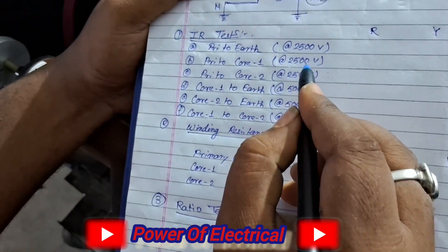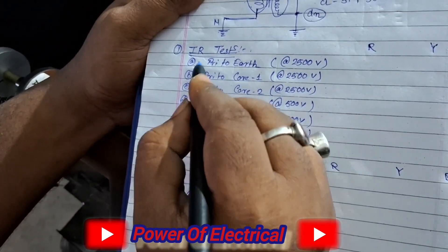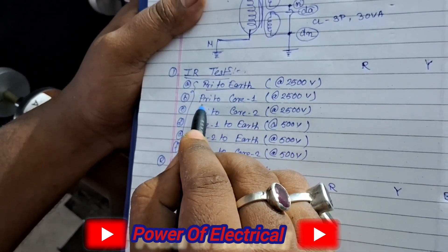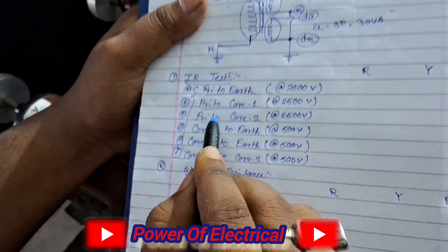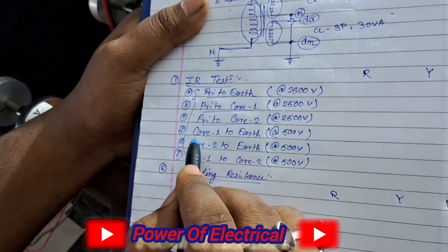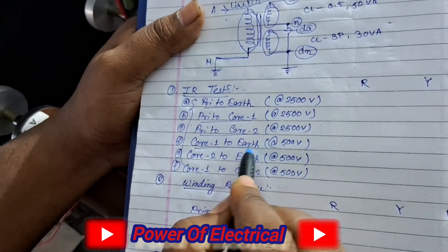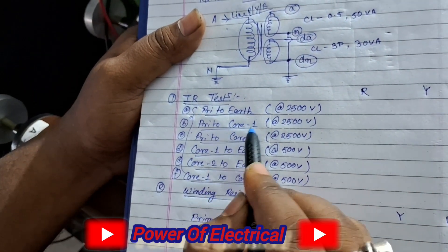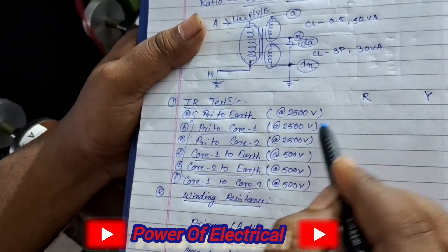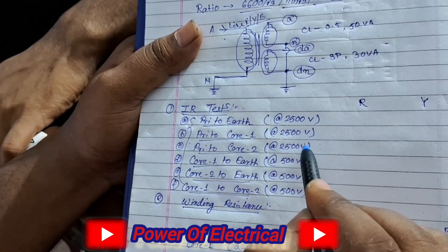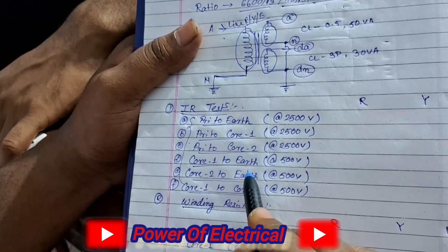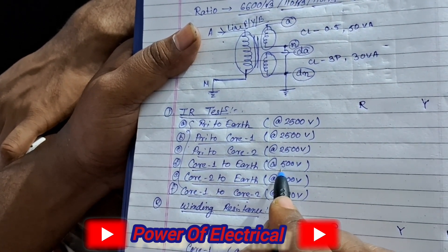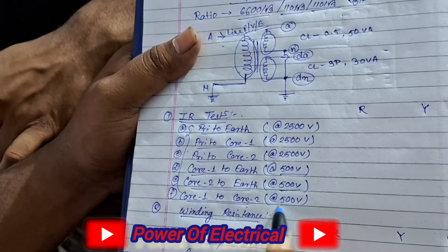For the IR test with a two-core secondary PT, there are six combinations. The first three are: primary to earth, primary to core one, and primary to core two. Then: core one to earth, core two to earth, and core one to core two. For primary to earth, primary to core one, and primary to core two, we apply 2.5 kV using a megger. For core one to earth, core two to earth, and core one to core two, we apply only 500 volt.